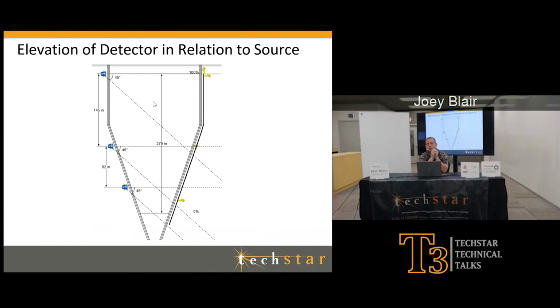Looks like I have two continuous level detectors. When you do this, there's actually an ability where they can put both of these detectors together to extend the length. So say I'm trying to measure 40 foot and I've only got a 20-foot detector, I can put both detectors together and make it one measurement, or I can do both of them separately. Depends on how I want to bring it into the house, right? I want to measure, say, 0 to 100% on the bottom detector, and then I know that when I'm leaving that bottom detector, it should be at 100, and then my top should start to fill, and you're just going to show 0 to 100. Some places decide to do it that way. That's how they prefer to see it. Other places say, I want that entire measurement. I want it to be 100 and 0 to be 0.